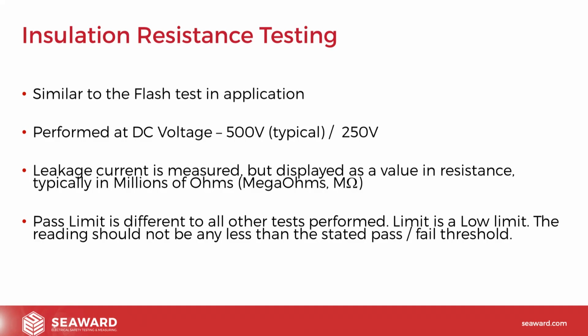So essentially, how does the test work? Well, we'll show you an animation shortly to show exactly what's going on during the test. But effectively, we strap the live and neutral test conductors together. We send the voltage up through the live and neutral conductors, and we then measure the return of any leakage current flowing down through either the earth cable if the product's a class 1, or via the probe if we're testing a class 2 product.